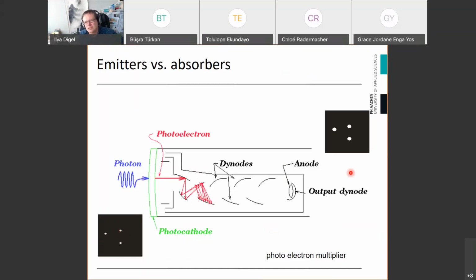And one of them is shown here in a system that many of you maybe already know. It is a photoelectron multiplier. So I have one single photon that enters this amplification system. It hits the target, and here one or two electrons will be set free, maybe one at the beginning. Then this electron will be accelerated by very strong electric fields as it goes from this point to this point.